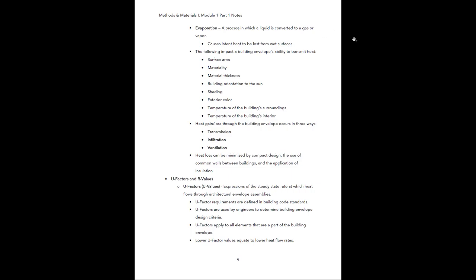Evaporation is a process where a liquid is converted to a gas or vapor; it causes latent heat to be lost from wet surfaces. The following factors impact a building envelope's ability to transmit heat: surface area, materiality, material thickness, building orientation to the sun, shading, exterior color, temperature of the building's surroundings, and temperature of the building's interior. Heat can be gained or lost through the building envelope via transmission, infiltration, and ventilation. Heat loss can be minimized by compact design, use of common walls between buildings, and application of insulation.